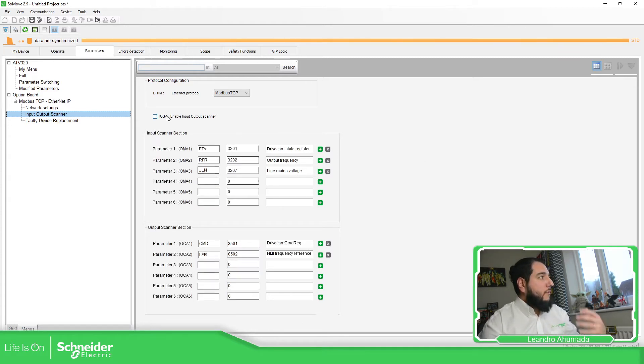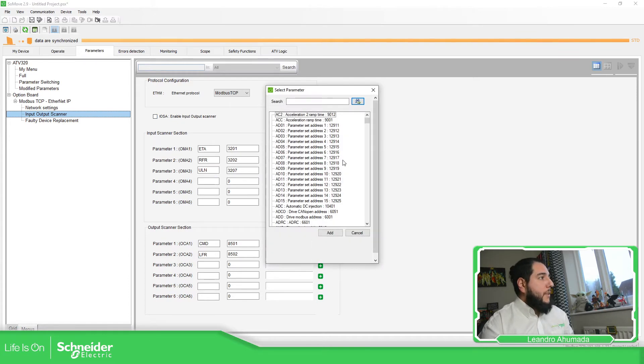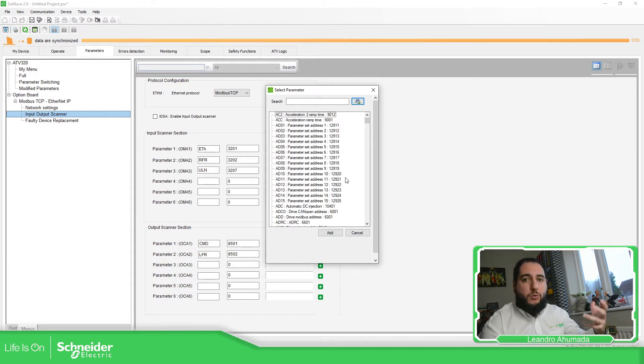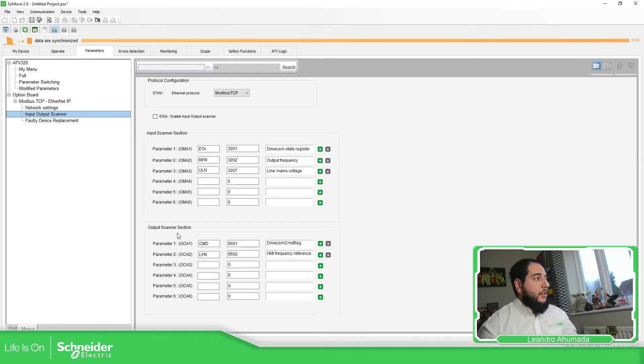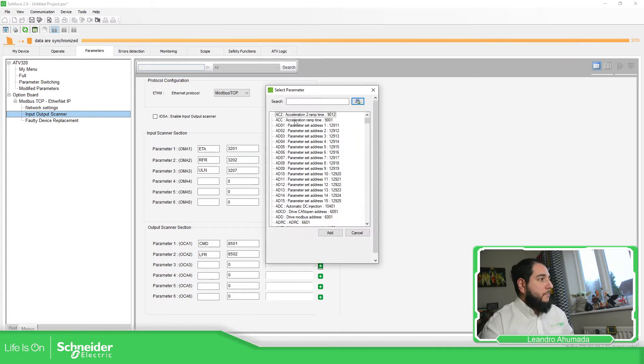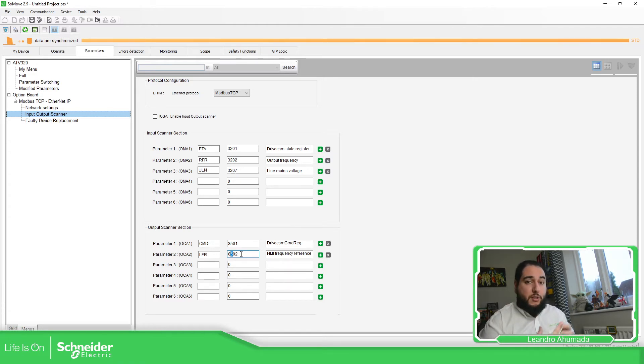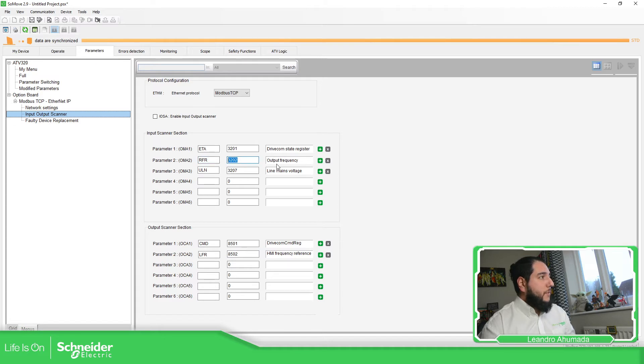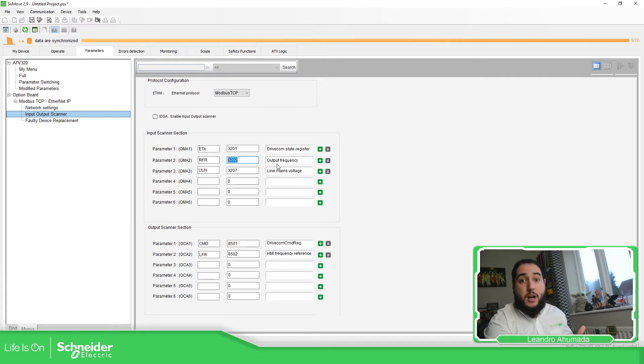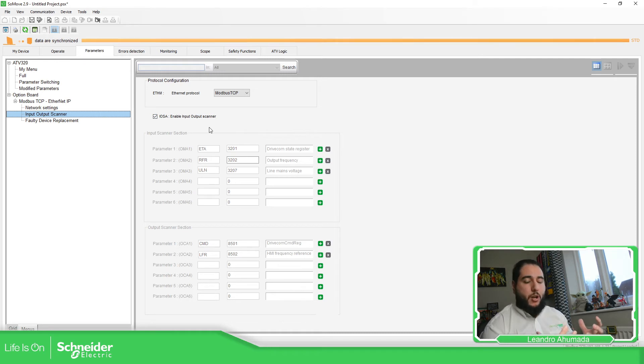For example, if I want to add something else, we just need to disable this and then go over here and add what we want to show. Simple as that — in that way you add more information to the channel. The same is for writing: if you want to modify something in the drive, you just need to add more information here. By default it comes with 8602, but instead of receiving the frequency it receives the velocity in RPM, so that is something we need to change. The same applies to the second parameter — instead of sending back the actual frequency, it sends the actual velocity in RPM.